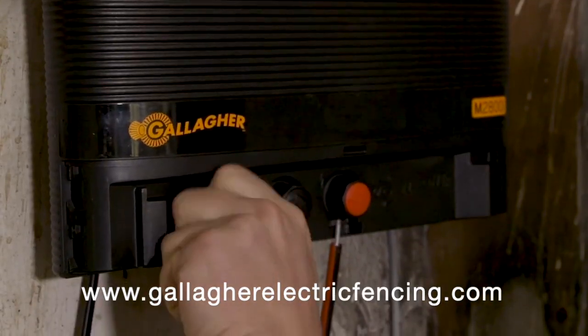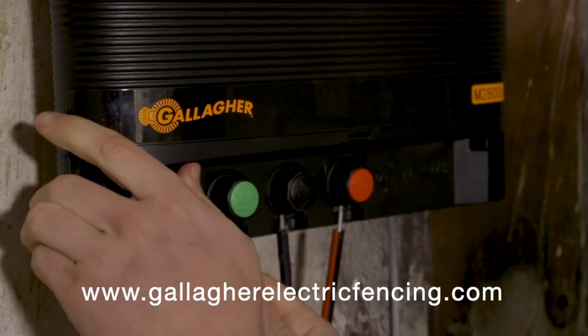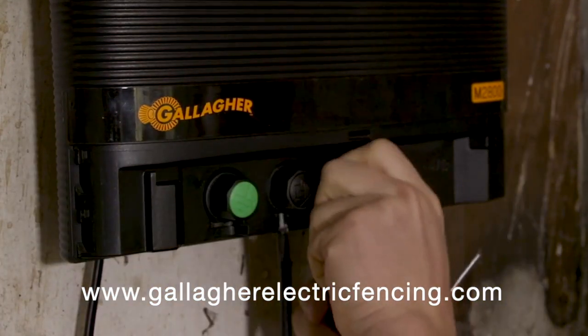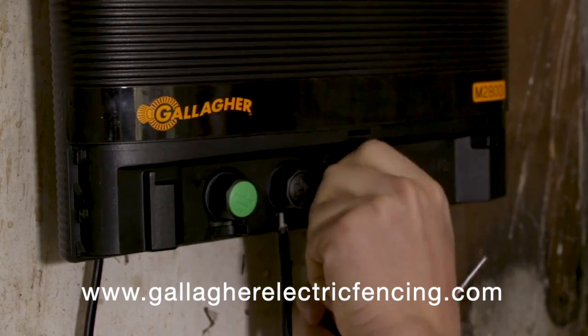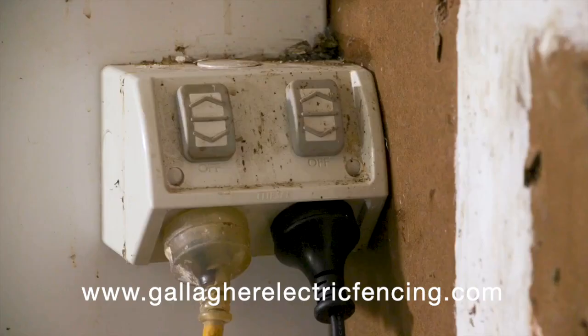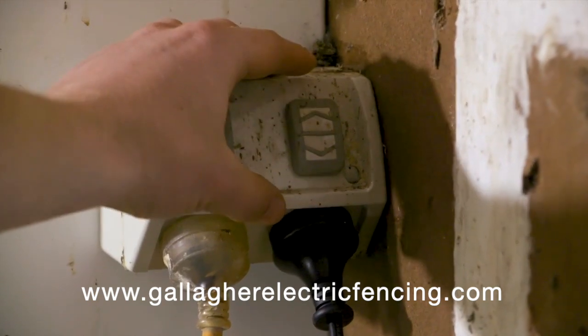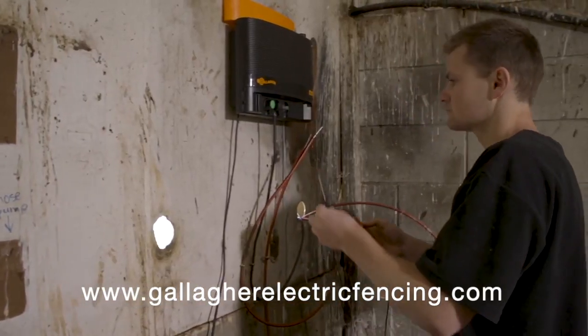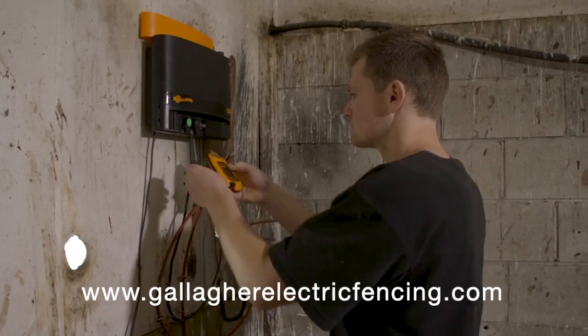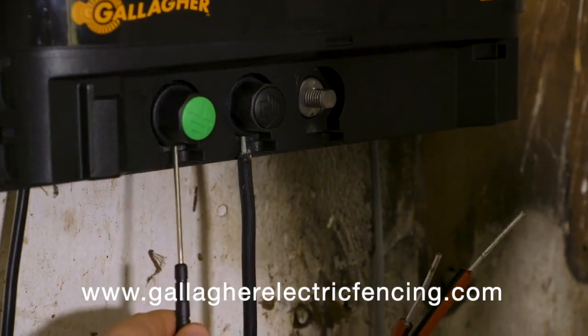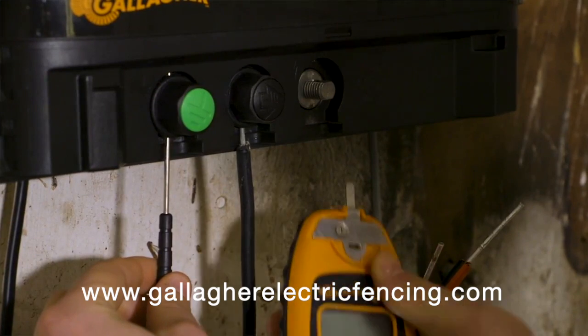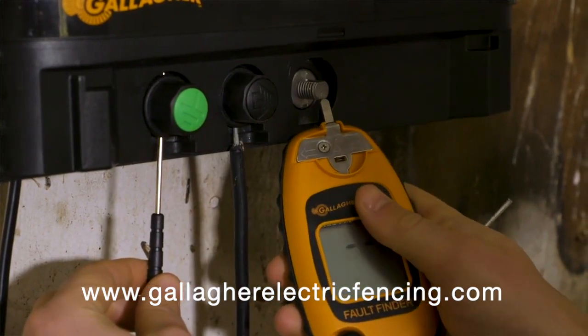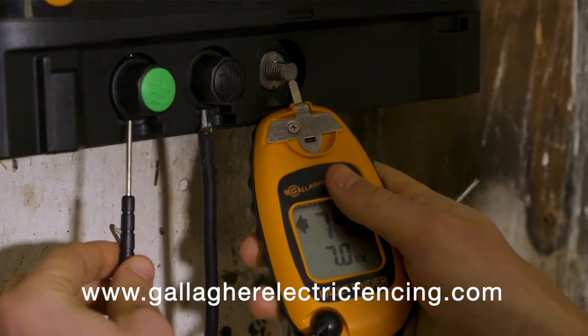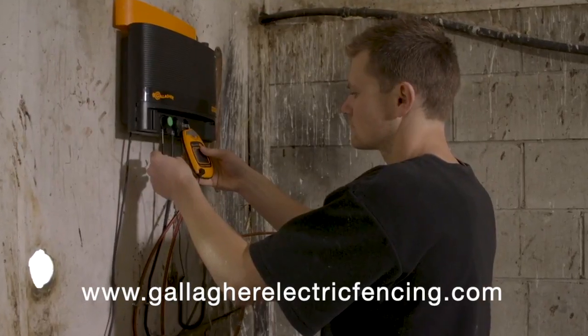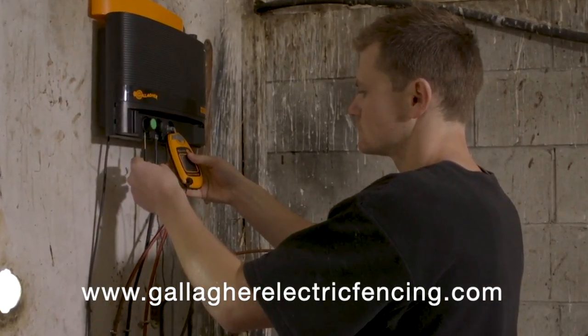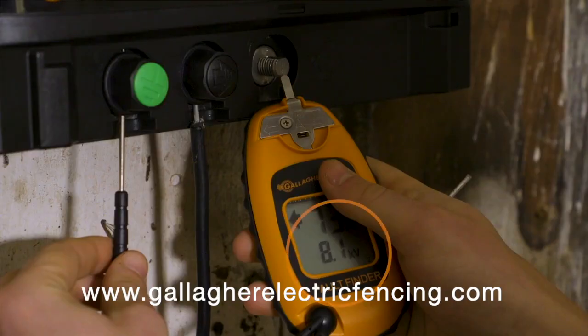Disconnect the ground cable or wire leading to the earth or ground system from the green terminal knob and the lead-out cable to the fence from the red terminal knob. Turn the energizer back on. Using your Gallagher fault finder, attach the earth lead, this is the curly cord, and place the earth probe onto the earth terminal. Then put the voltage probe, which is on the fault finder, onto the red fence terminal. The reading tells you how well your energizer is working without any other variables.